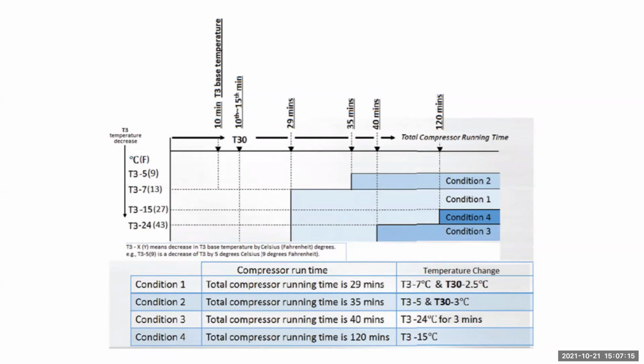To exit defrost, any of the following conditions will terminate defrost and return the unit to normal. The T3 temperature sensor rises above 59 degrees or remains above 46 degrees for more than 80 seconds. This will bring it out of defrost. The unit also stays in defrost for a total of 10 minutes. Condition 4 in this case is the cumulative runtime.